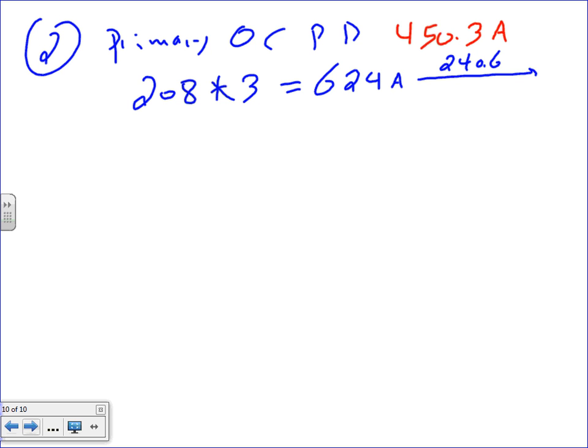By the way, can you go up? Is there a Note number 1? Yes. So if it's not a standard size, that will leave you with a 700 amp fuse or circuit breaker. In this case, fuse, because we're using fuses here. What's the multiplier for a circuit breaker? 2.5? Circuit breaker on the medium voltage side, or is it the same? 600. Okay, so we're using a fuse. That's why it's 3. Had it been a circuit breaker, that would be a big one.